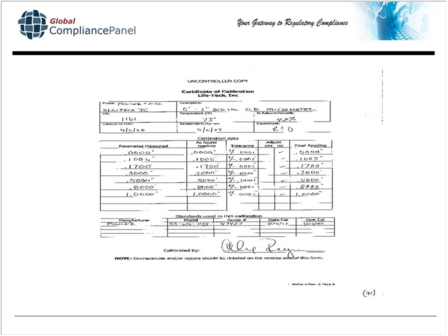So it's very interesting to look at this as far as how you set. You can see here the parameter measured based on the as found, the tolerance, and the final reading. So it sets forth here what parameters are going to be used. And then the second section, where it says standards used in this calibration, references the manufacturer, the model number, the serial number. So I can tie the standards used in this calibration to the actual standards that have been sent out to another firm.